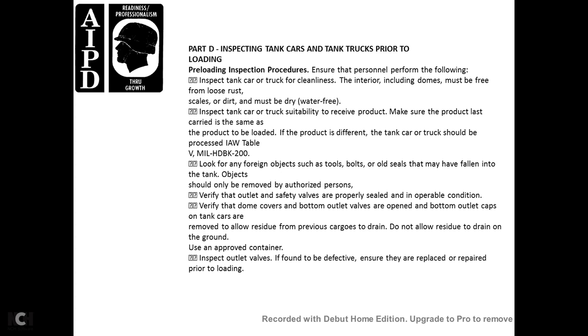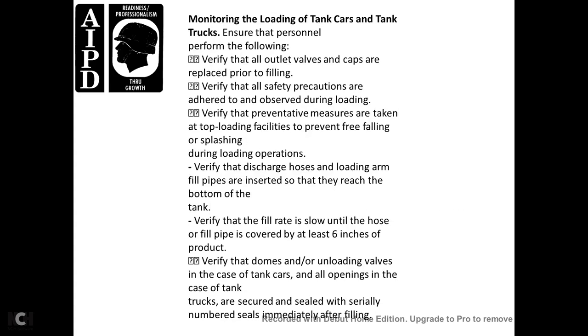Inspect outlet valves; if found defective, ensure replacement or repair prior to loading. Monitoring loading of tanker cars and trucks: verify outlet valves and caps are replaced upon filling; verify all safety precautions are observed during loading; verify preventive maintenance measures at top-loading facilities to prevent free-falling or splashing during loading. Verify discharge loading arms and fill pipes are inserted to reach the bottom of the tank. Verify fill rate is slow until the fill pipe is covered at least six inches. Verify domes, unloading valves, and all openings are secured and serially sealed immediately after filling.